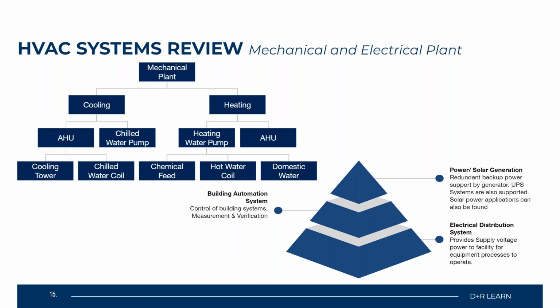Now, you have different types of systems used in your cooling applications, such as package units, which could be supplemental systems also used to provide comfort cooling. DX systems are another example, used to provide supplemental cooling to a cooling system where chillers are the main application. You also have domestic water treatment and distribution at your mechanical plants, where water is chemically treated and the pressure is regulated before any distribution to the facility. Whether that is a commercial office facility or a residential facility, maybe an apartment complex, water treatment is extremely important because you have to regulate the pressure and the quality of that water. All of those items will be maintained within your mechanical plant.